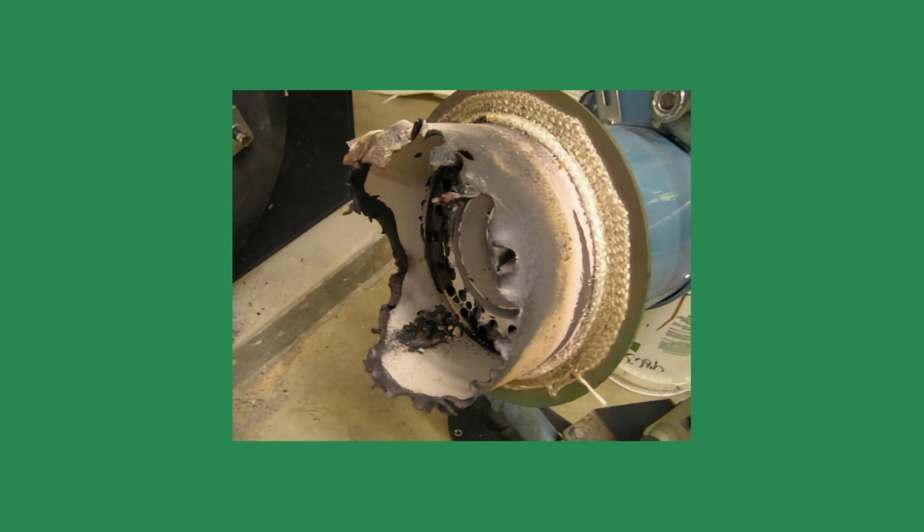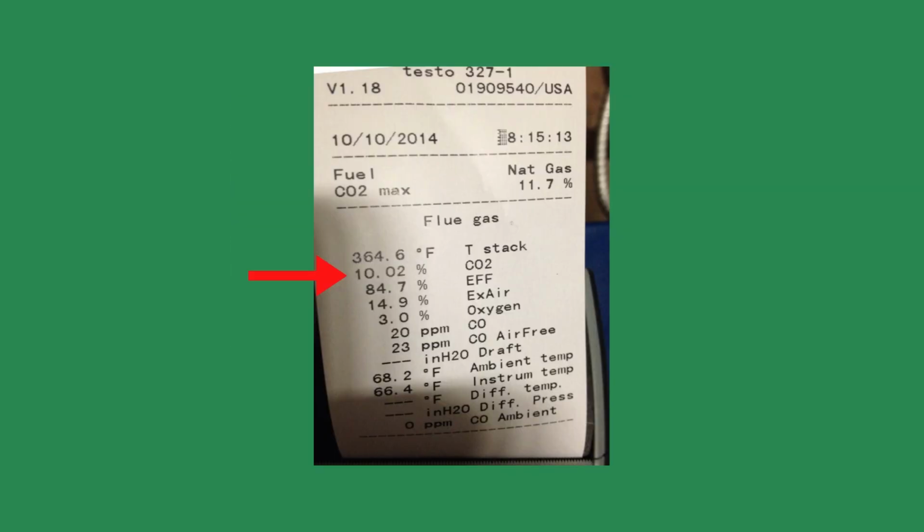I smiled. So what do we do? Replace the boiler with a smaller one, he asked, and I explained that would be the ideal solution, but, as typical, money is tight. My solution is twofold. Pointing to the combustion report, I showed him the carbon dioxide or CO2 readings and said, You have the air-to-fuel ratio set to the high fire settings.